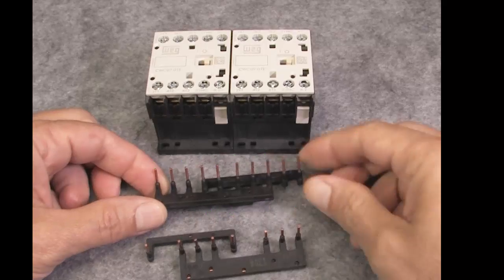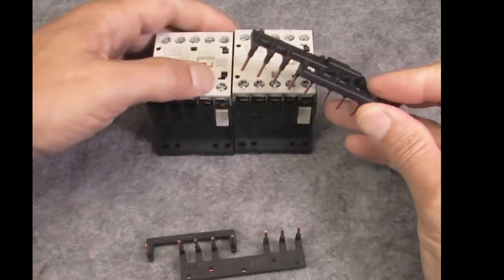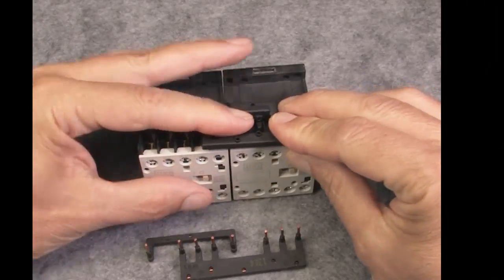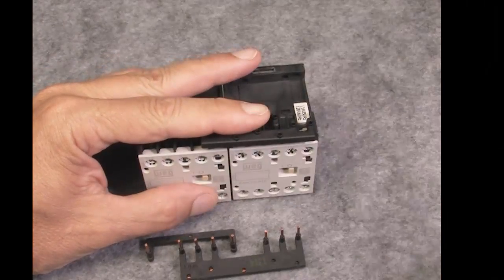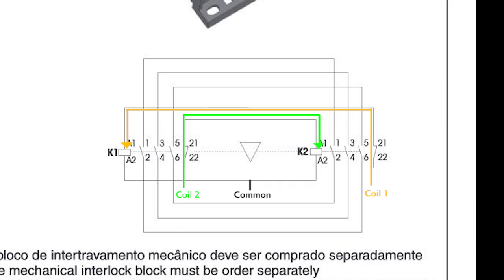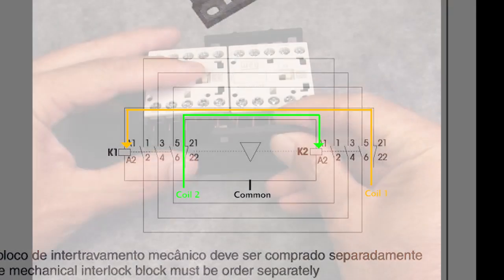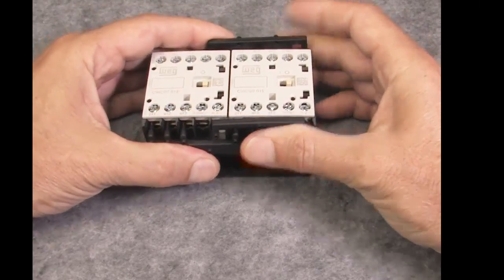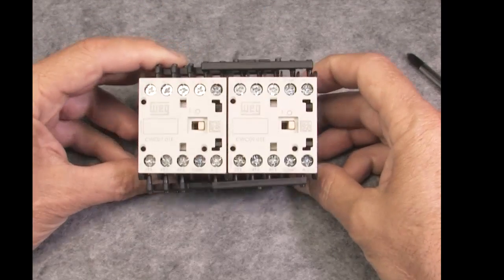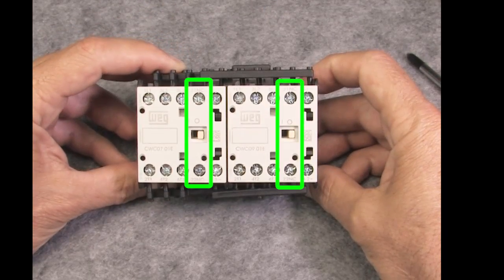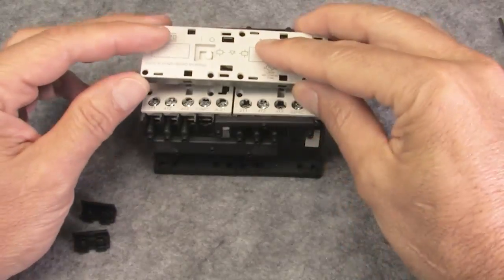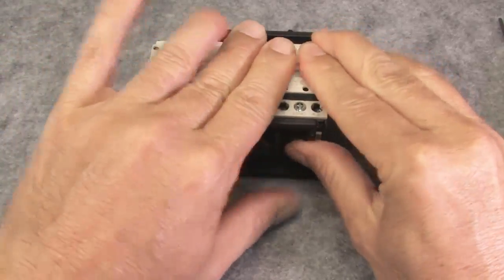Well, since the 3 pole WEG contactors have aux contacts built in, all of the wiring for the electronic interlock is built into these modules. If you look at the wiring diagram on the reversing kit documentation, it looks just like the diagram we had earlier doesn't it? Except now we don't have to add any aux contactors or do any of the wiring ourselves. You do need to make sure you get contactors with a normally closed aux contact. The mechanical interlock is provided by this module which just snaps in here.